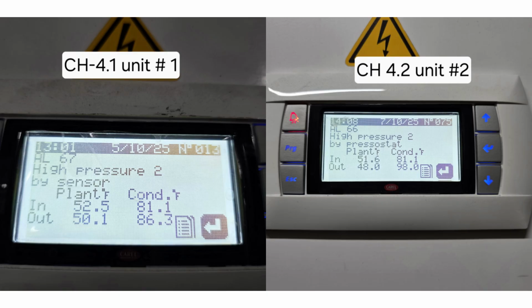A high pressure alarm happens when the refrigerant pressure in the condenser becomes too high. In simple terms, the refrigerant can't reject heat properly with the air or water. Here are the most common causes: dirty or clogged condenser coil in an air-cooled system, and condenser fan not running or running at low speed. In a water source system, low condenser water flow, closed valve, or a dirty or clogged condenser heat exchanger. Overcharged refrigerant, or the presence of non-condensable gases like air in the refrigeration circuit. High outdoor ambient temperature, or poor ventilation around the unit.